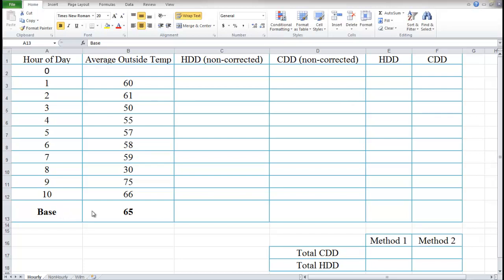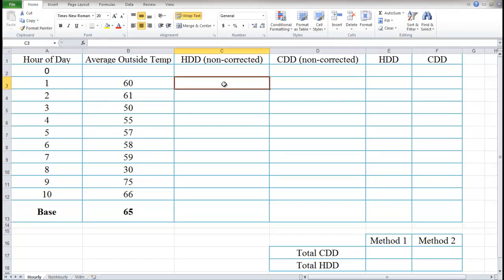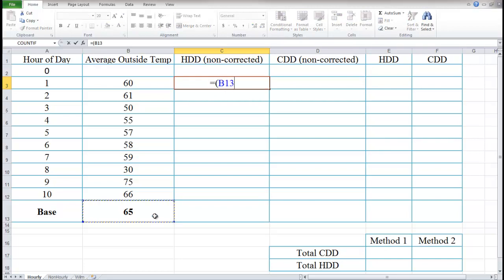One thing to point out is I have the base down here at 65, but I'm going to make this Excel sheet so that if I change this base, it will automatically change my calculation for heating degree days and cooling degree days. So the first thing I'm going to do is start with heating degree days, which equals the base minus the outside temperature, divided by 24.